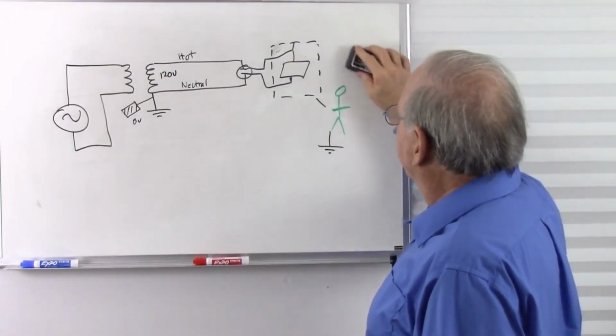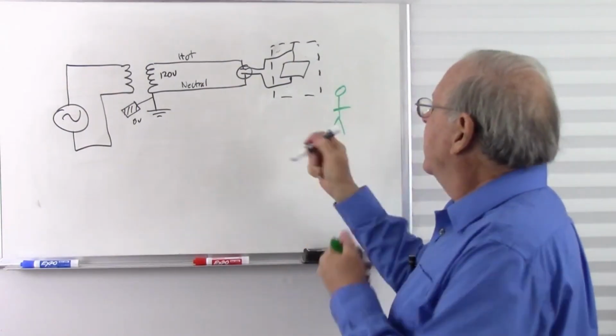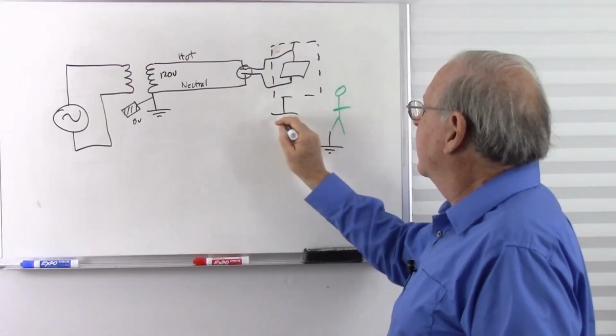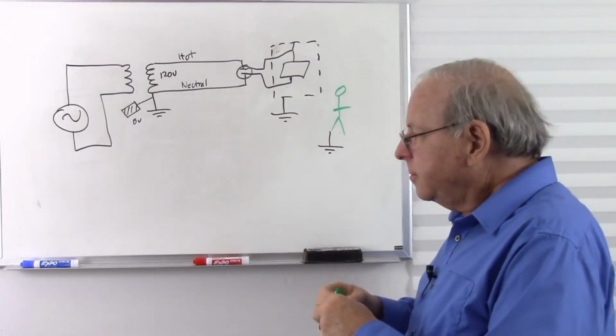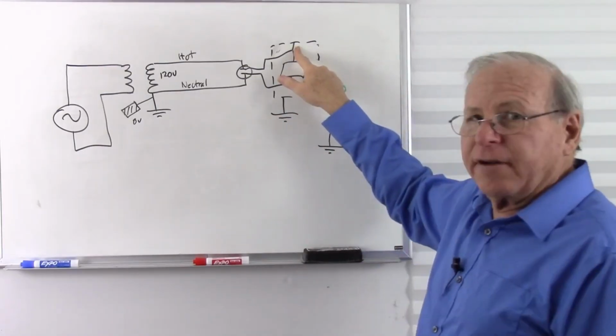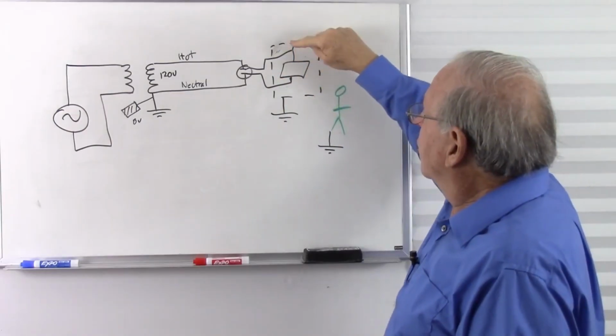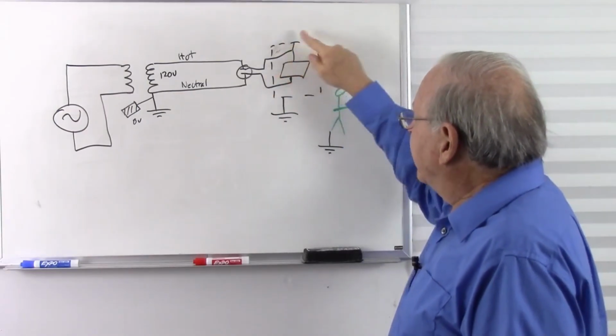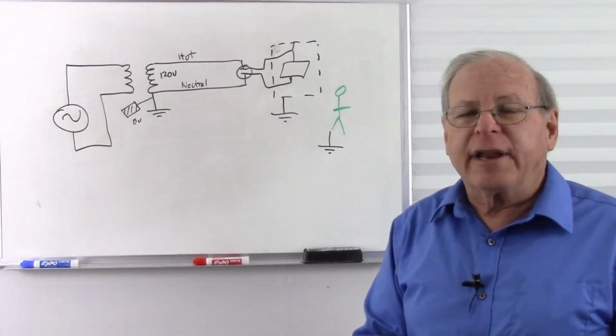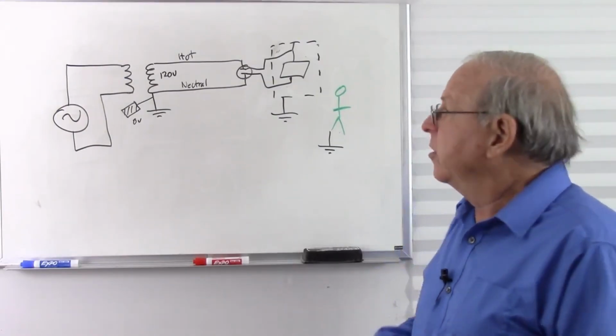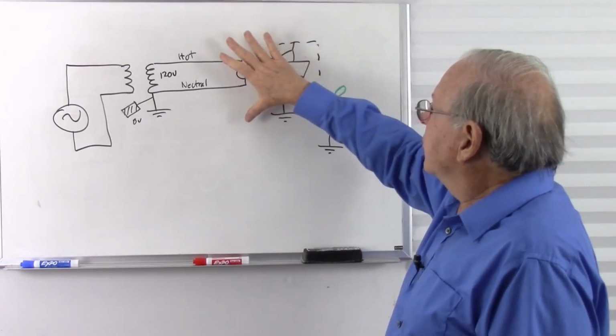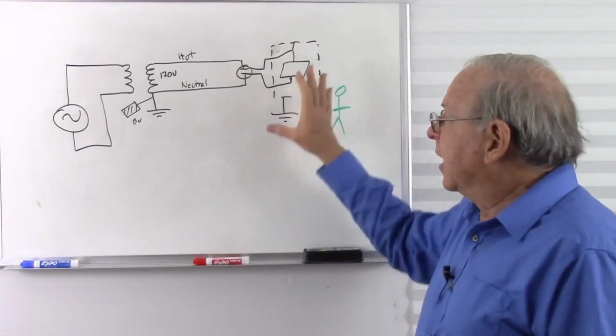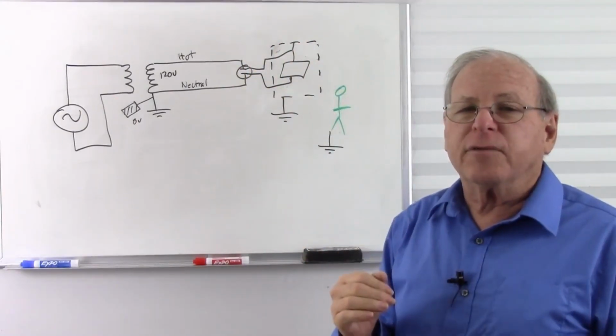So what do we do? Well, of course, I'm leading up to this. We ground that box. Now, should I get that fault, I'm going to get current going through that metal chassis straight to ground. And that's going to have a very, very low resistance. So what that means is, even though I may get a high current, that low resistance means it can't build up enough voltage to be dangerous.